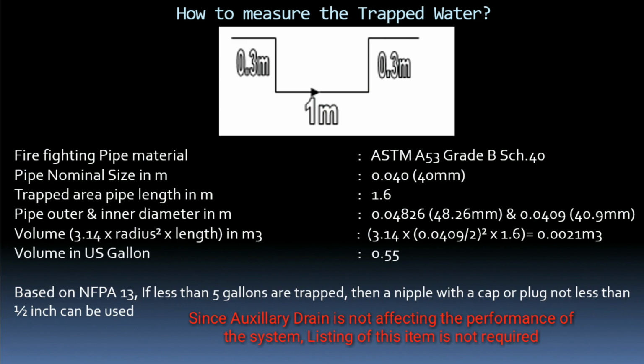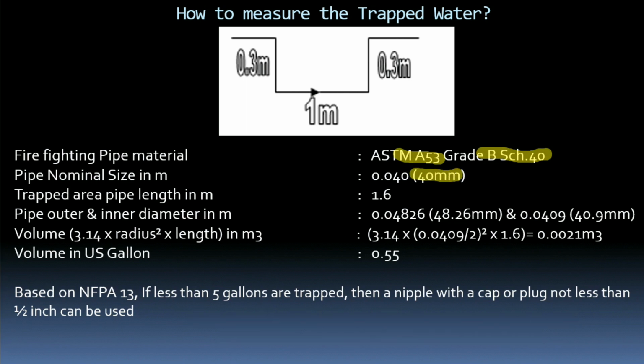So here we are using firefighting pipes, ASTM A53 Grade B, schedule 40 thickness, and the nominal pipe size is 40 mm. You know that for ASTM A53, the nominal size means the inner diameter and outer diameter both will not be 40 mm. There will be slight differences based on the schedule. When it comes to chilled water pipe sizing, I will explain this in detail. For the 40 mm nominal diameter, the outer diameter is 48.26 mm and the inner diameter is 40.9 mm. As I mentioned, both the outer and inner diameters will not exactly match the nominal size.